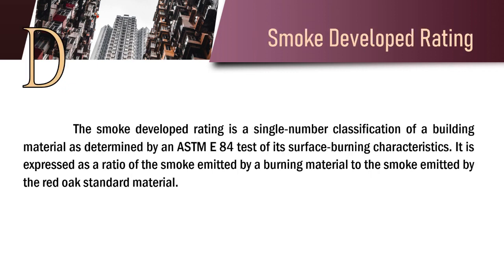The last rating is the smoke developed rating. It is a single number classification of a building material as determined by an ASTM E84 test of its surface burning characteristics. It is expressed as a ratio of the smoke emitted by a burning material to the smoke emitted by the red oak standard material.